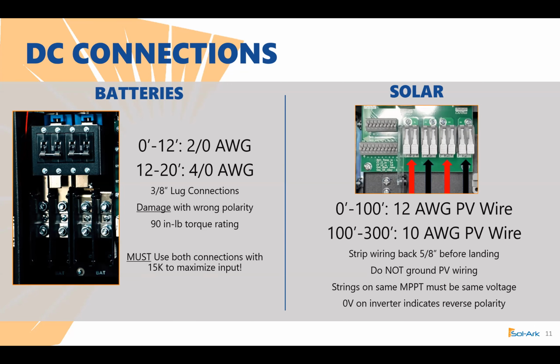For the solar connection, for that wiring, you can do about 12-gauge wiring from 0 to 100 feet, but we can extend it all the way to 300 feet before there's an unacceptable voltage drop, I think about 3%. You can use 10-gauge wiring. Now, let's say your array is much further away, 400 or 500 feet. What you're going to do is probably combine the array upstream. Once you combine it in a DC combiner panel, you'll just use a larger gauge wire, run it to the inverter, 400 and 500 feet away, and then split that wire back to an acceptable gauge so they can actually connect to our MPPT connections.